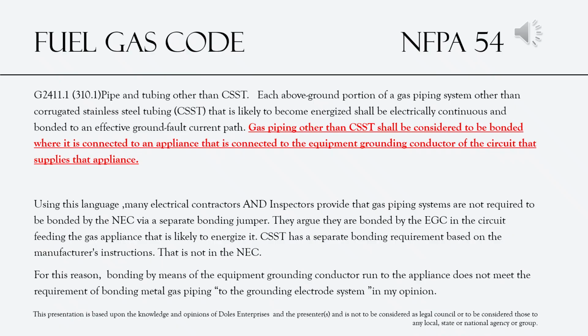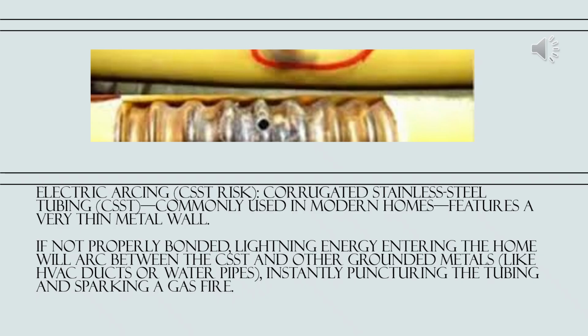I used to be like everyone else. I considered the fact that if the equipment had electrical connections somehow, the equipment grounding conductor that was there was sufficient. But as I research this more and more, I see now the reasoning behind requiring the bond. And since we're talking about it, we're going to talk a little bit about this CSST. The problem you have, like in the picture you see, is an arc that occurred from a lightning strike nearby at this house. Electric arcing and the CSST risk.